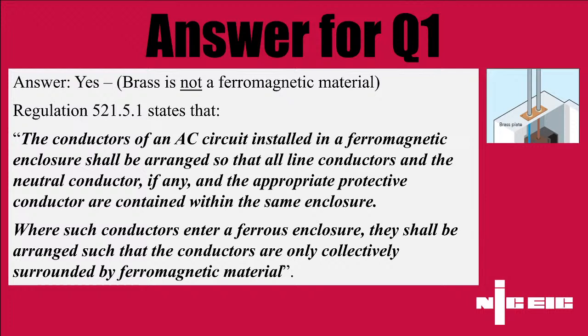And touching on the regulation, 521.5.1 of BS 7671, ferromagnetic enclosures and electromagnetic effects, this reinforces that the AC circuit line conductors and the neutral, and any appropriate protective conductor, should be collectively surrounded by that same material. That's because it is ferromagnetic. But when it's something like brass, it doesn't count.